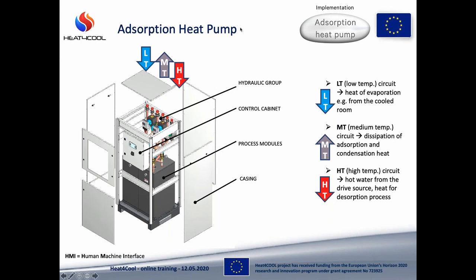The main components of our adsorption heat pumps are the process modules. It's always an even number of process modules, so either 2, 4, 6, or 8 of them. Then there is the hydraulic group, which consists of pumps and three-way valves directing the HTF at the right temperature levels to the corresponding heat exchangers. We have a control cabinet with a human-machine interface, and of course we have a casing with frames.